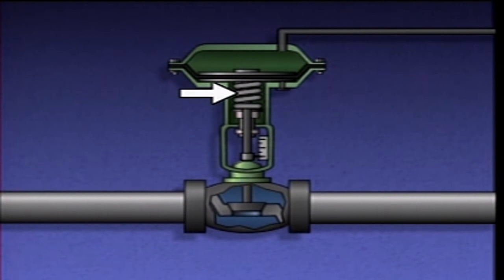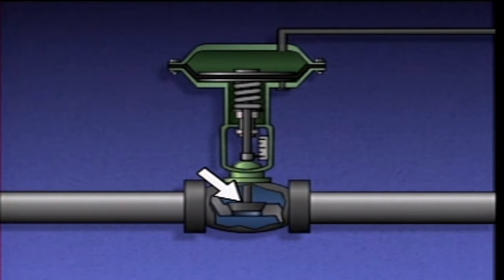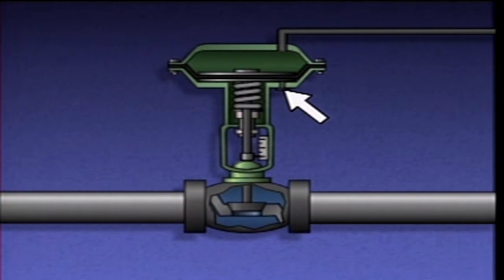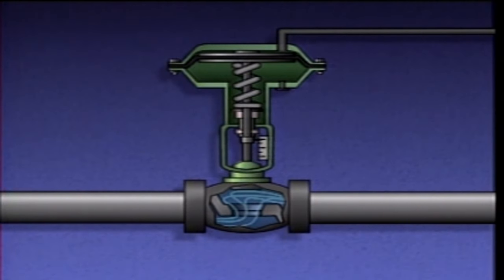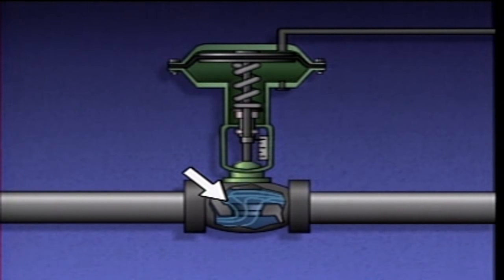The spring is compressed and the valve closes. Air in the lower chamber is exhausted through the air vent. When air pressure to the upper chamber is reduced, the spring moves the actuator's stem upward and the valve opens.